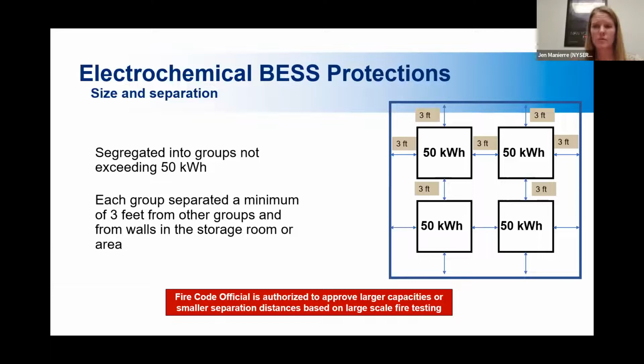And this is, like I said, one of those examples where, based on that large scale fire testing in the red box on the bottom here, the fire code official can say, okay, I see the results show 100 kilowatt hour blocks 3 feet apart are shown to be safe. So yes, you can do that. Or they might see as a result that 50 kilowatt hour blocks spaced 2 feet apart are fine. So they have a little bit of wiggle room there based on the results of the testing. But the default in the code is what you see here on the screen.